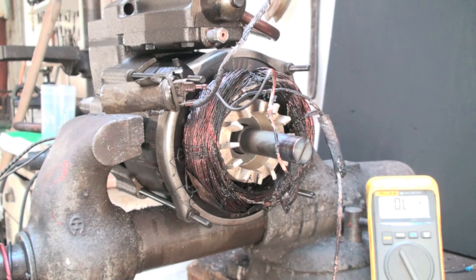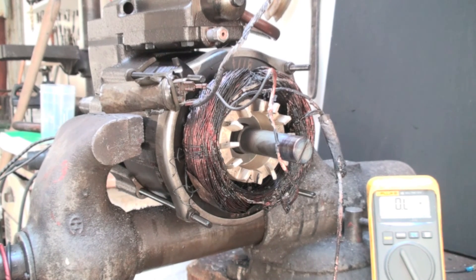This thing would have certainly had phosgene gas — if you open one of the taps, you get phosgene gas out of it. That should tell you at that point that there's nothing you can do; this thing is dead. So the simple test of phosgene gas was probably the most valuable test on this thing, because this thing is not showing a short to ground — it's just showing an open.